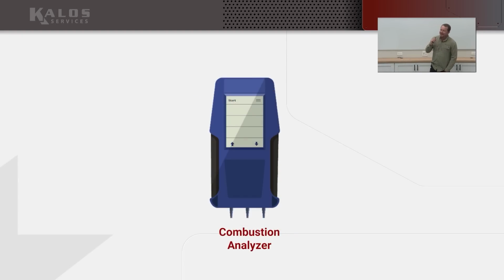Combustion analyzer is there to actually test the flue gases themselves, to look at: do we have unsafe levels of carbon monoxide, do we have complete combustion going on? And that's actually a really important thing. It also can tell us things like flue draft, whether we're under negative or positive pressure in the flue. And it can tell us about our oxygen mix, all that kind of stuff. And that's a skill that you have to develop, that you have to be trained in. It isn't overly complicated. You're literally just taking a probe and sticking it into the flue. The biggest challenge is that manufacturers, because sometimes they're just idiots, don't give us a place to actually test for combustion. So we actually have to make a penetration into the flue in order to measure.